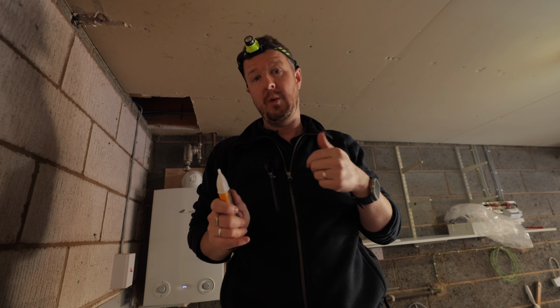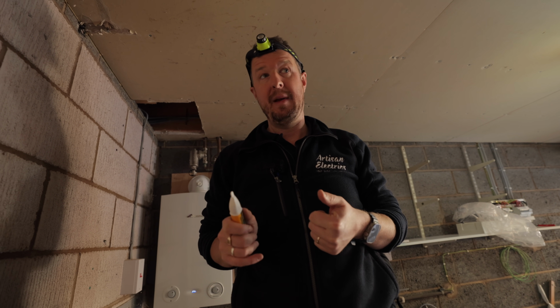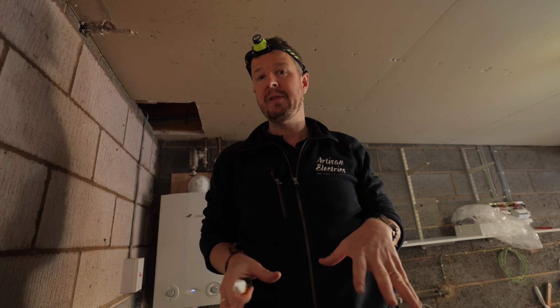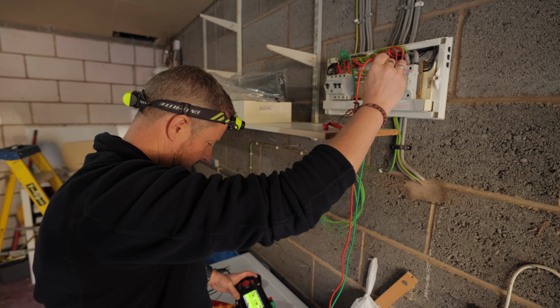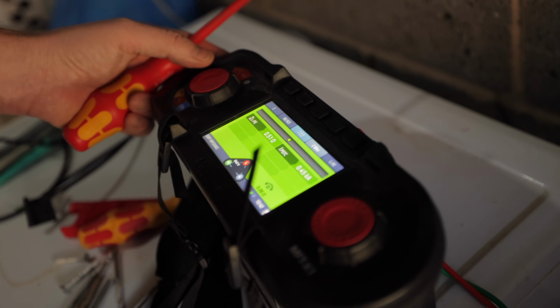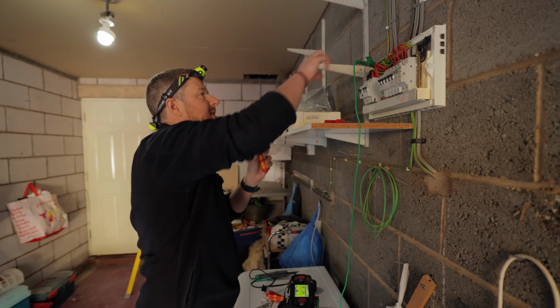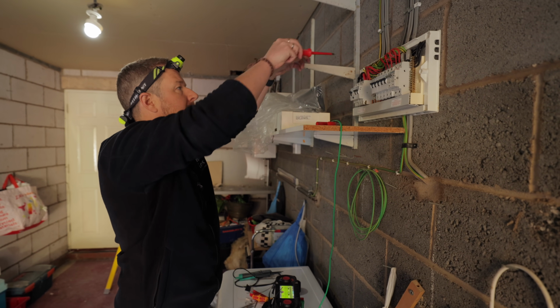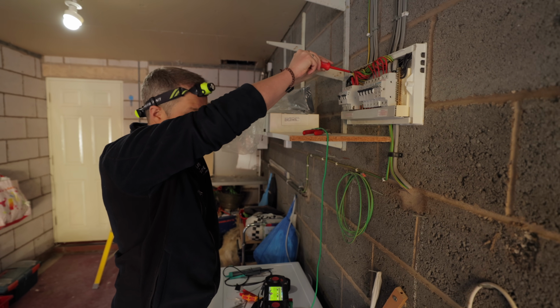So what we're going to do is an external earth fault loop impedance test and actually check that this whole house is earthed properly. That might be the cause of the issue. This could be the problem. We got 0.51, which is quite high, assuming that it's a TNCS system, which it probably is here. So that's where you've got combined neutral and earth.